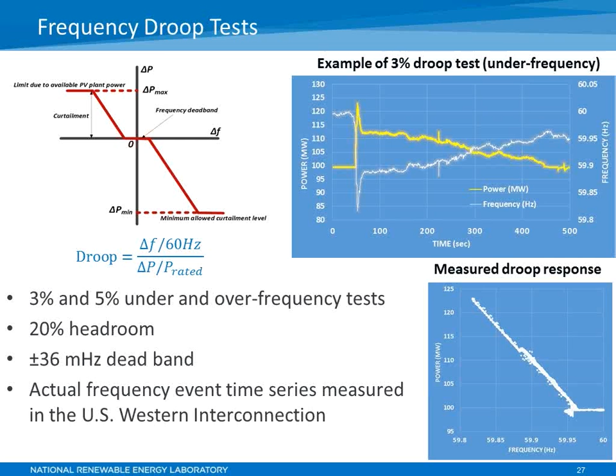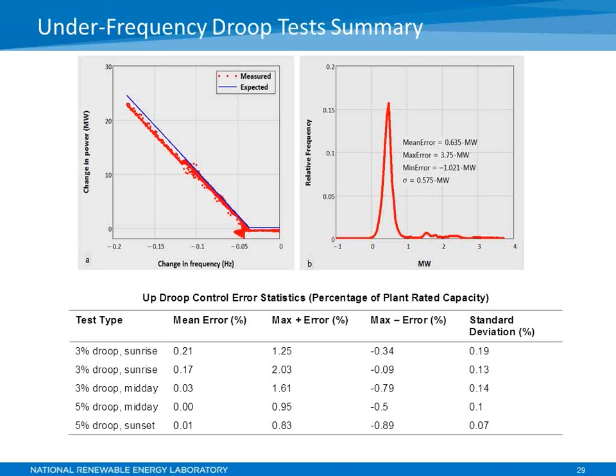So this is a summary of many tests we conducted under different resource variability conditions during different times of day, with different droop settings. And this table summarizes the mean error and some statistics of the control error when the plant is providing the droop response. This is all expressed in percentage. If you translate it into megawatts, you see that it's a very small error. So the accuracy of its response is really remarkable, and it's much better than many conventional technologies can ever provide.